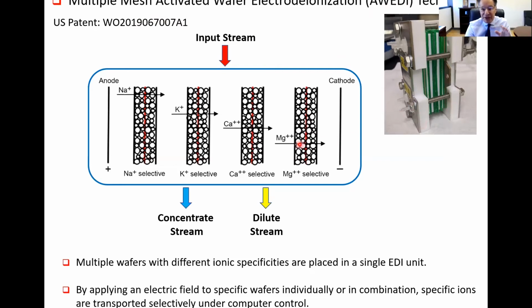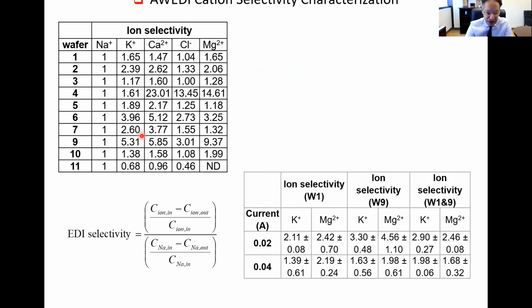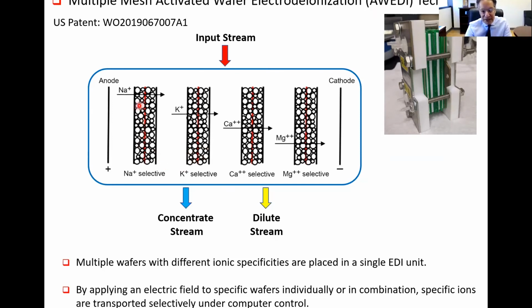And the unique thing about this, as opposed to other electrodeionization devices, is it combines multiple ion selective resins into one device. So we have sodium selective ion exchange resin, a potassium selective, calcium, magnesium. What this allows you to do under computer control is to selectively choose the transport, the ion that you want to be transported alone or in combination. It provides functionality and also saves a lot of space compared to having a different EDI unit for each of these.